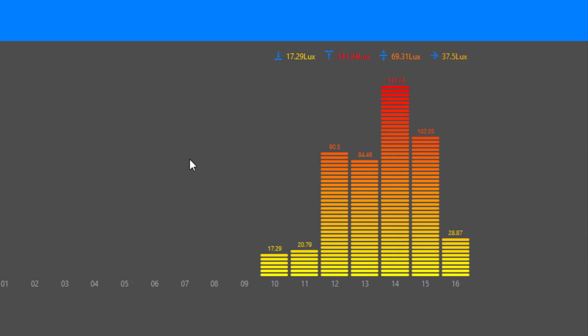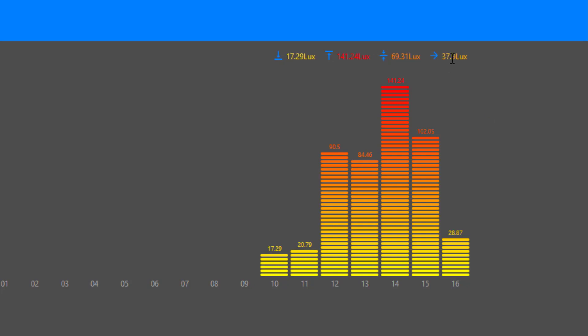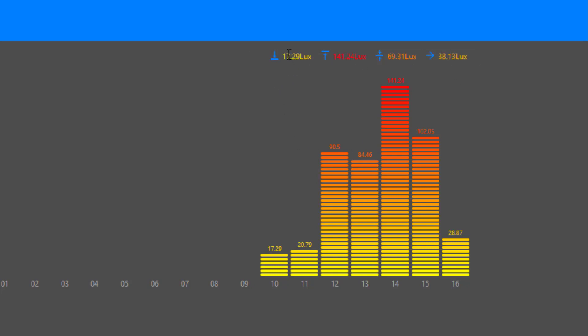So this is the last period it calculated. The period it's working on at the moment, so 5 o'clock here, is this information here. So I can see that my current average value is there, 69. Sorry, it's jumping around a bit. That's my current value. So that's my process value coming in with no averaging. And then I have my maximum and my minimum value during that period. That's a nice little node that gives you a visualization for averaging. That can be quite powerful as a long-term indicator.